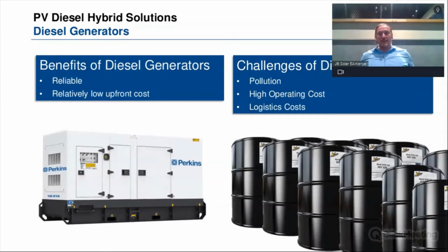But then there's also maintenance on your diesel engines. They have to have regular maintenance. In fact, ideally you should have more than one diesel generator, because one is running while the other is being maintained, and then you switch to the other and maintain the first. So you require a technician on site almost all the time, and the operating costs are quite high.